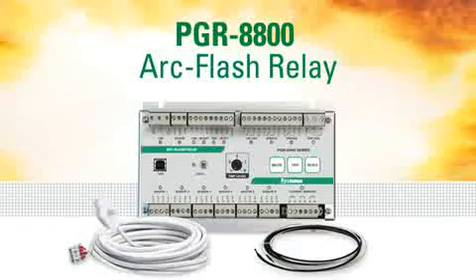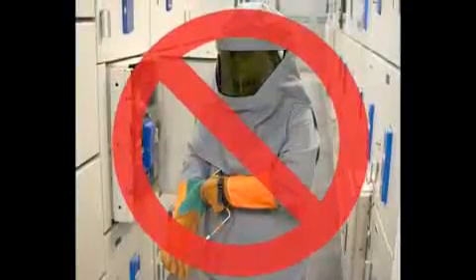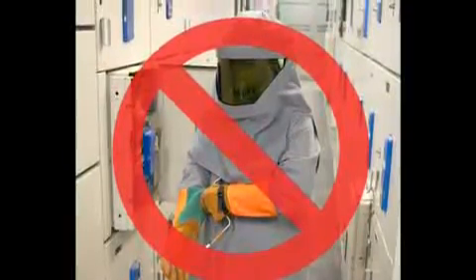This was illustrated when Evans Enterprises in Tulsa, Oklahoma, was trying to minimize the hazard risk category of a cabinet that exceeded level four. This meant a worker could not approach the cabinet if it was open.